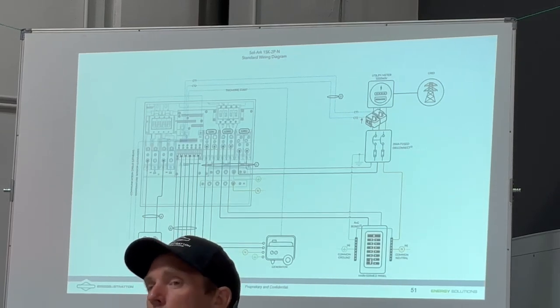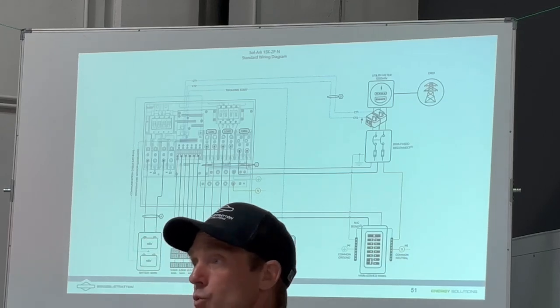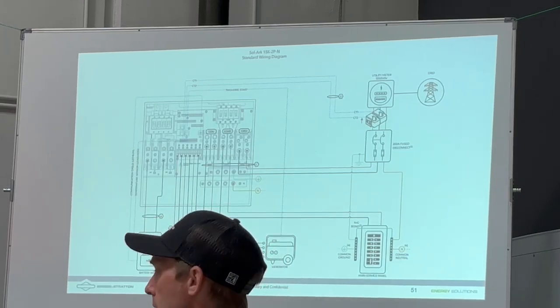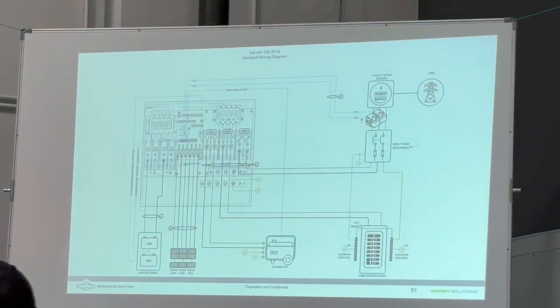But you could also just leave that transfer switch on the wall and allow power to come from the transfer switch into the grid port on the inverter. And the inverter is smart enough to know the difference between when the generator is powering it and when the grid is powering it. The reason it knows that difference is, like I told you earlier, a generator has less stable voltage than the grid. The generator's voltage can vary up and down a little bit. So these are the two wiring diagrams for that.